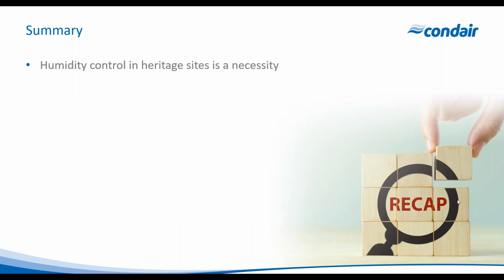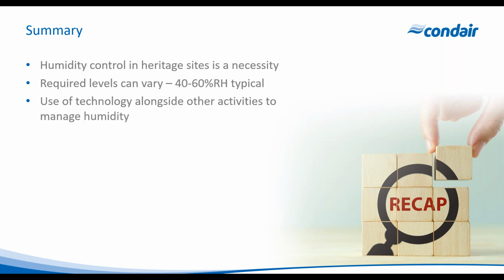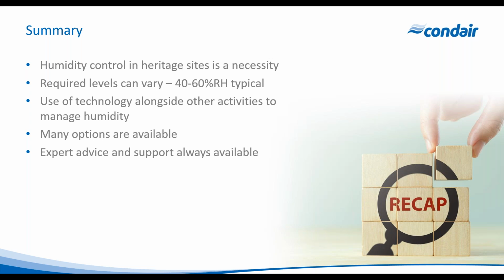So in summary, we looked at humidity control in heritage sites. It's a necessity. We know that as we're putting moisture into the air from outside, unless the moisture content outside is equivalent to the required absolute internally, we've got an adjustment to make. The required humidity levels can vary between 40 and 60% typically. And use of technology alongside other activities to manage humidity is critical, and many options are available depending on the application, the energy source available to you, and the existing infrastructure of the building as far as the HVAC system is concerned. And of course, expert advice and support is always available from ourselves.